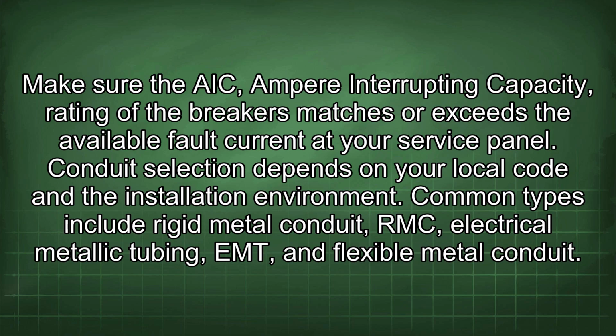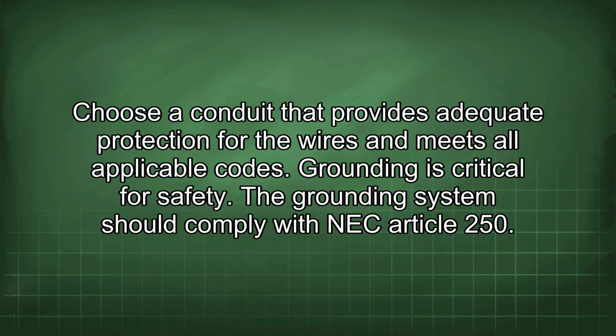Conduit selection depends on your local code and the installation environment. Common types include rigid metal conduit, RMC, electrical metallic tubing, EMT, and flexible metal conduit. Choose a conduit that provides adequate protection for the wires and meets all applicable codes.